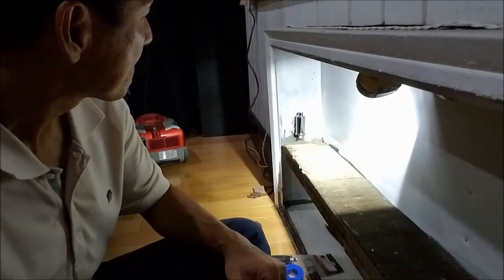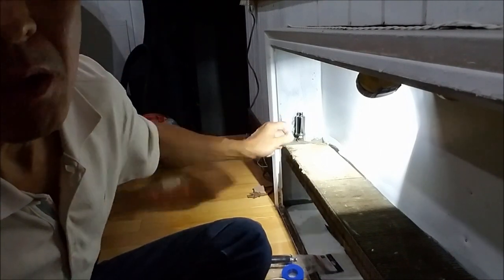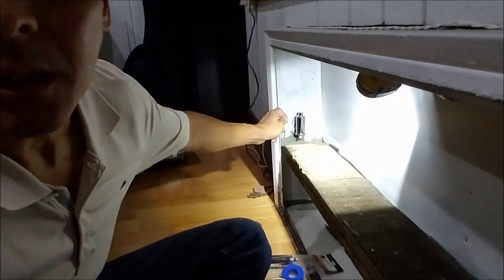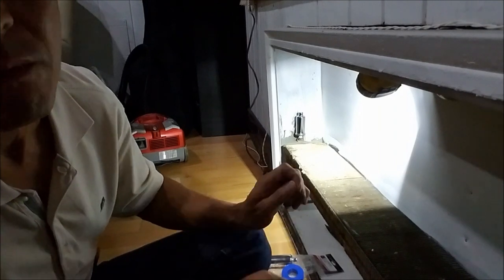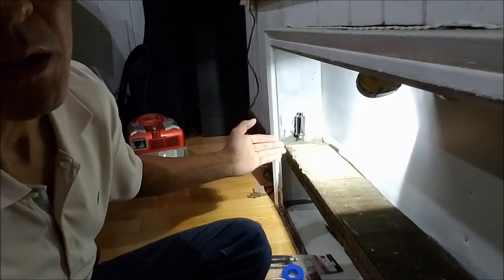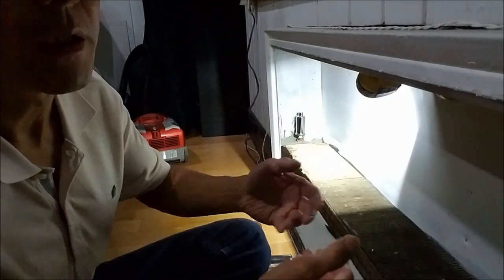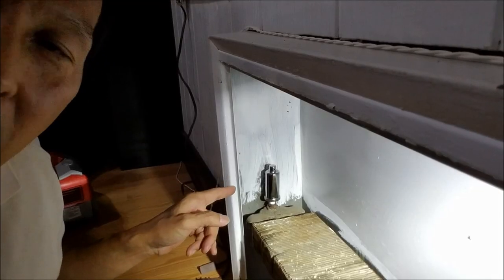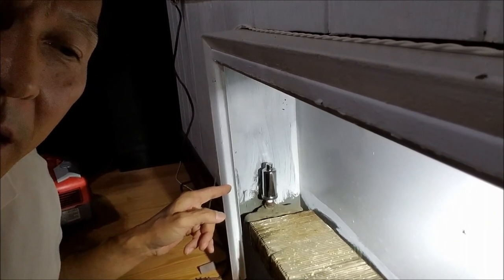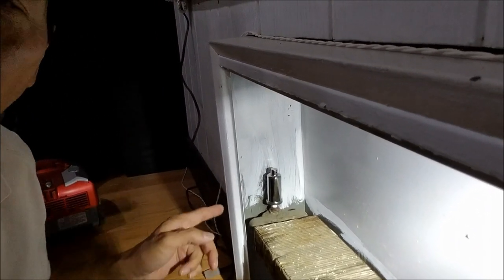So even though steam spits out from here, maybe for a few seconds, like 1 or 2 seconds, it's just a very, very small amount. It's a very small amount of steam, so that steam has the chance to flow into the radiator to heat up the radiator for the room. It escapes a little bit, not much like the one before. You see? Yeah, I can hear just a little bit. And now it stops. Okay, that's normal.